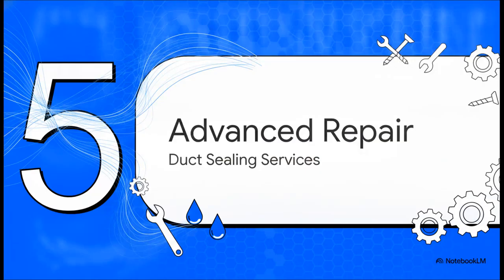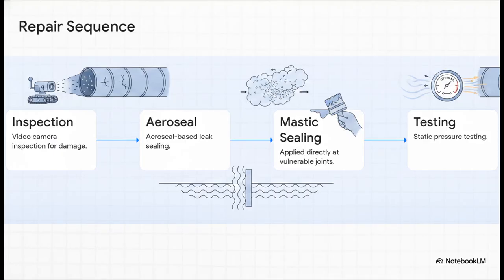Section 5, Advanced Repair and Sealing. Here's the kicker: if you have leaking air ducts, your HVAC efficiency plummets, and that 77% outside humidity we talked about comes rushing right back in. So here's the advanced repair sequence Bright Air uses to systematically eliminate that threat. First, a video camera inspection to pinpoint the exact locations of any leaks or damage. Next, they utilize AeroSeal-based leak sealing technology and apply mastic sealing directly at the joints, since those are the most vulnerable parts of any duct system.